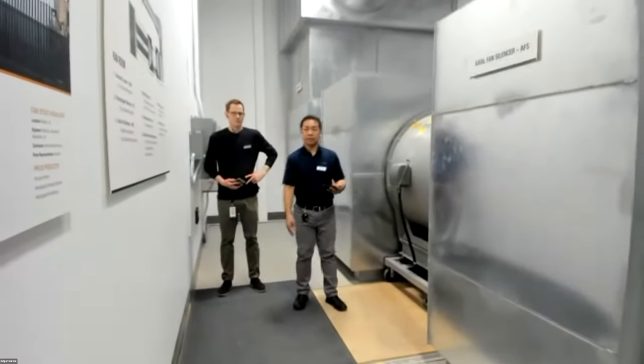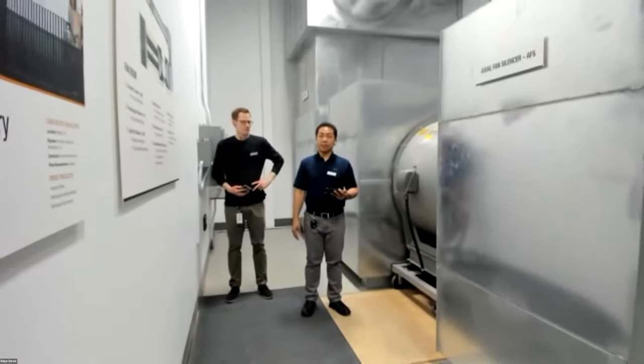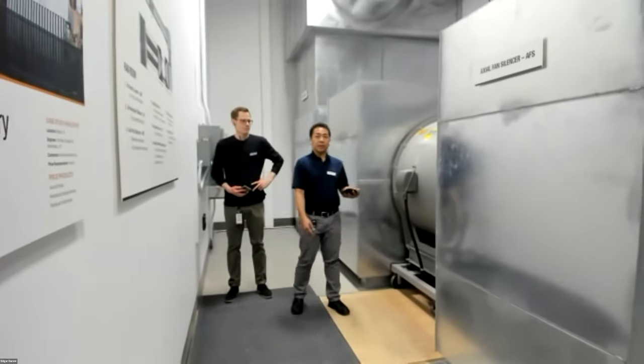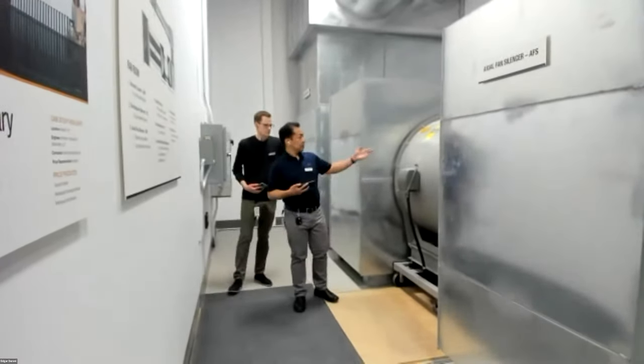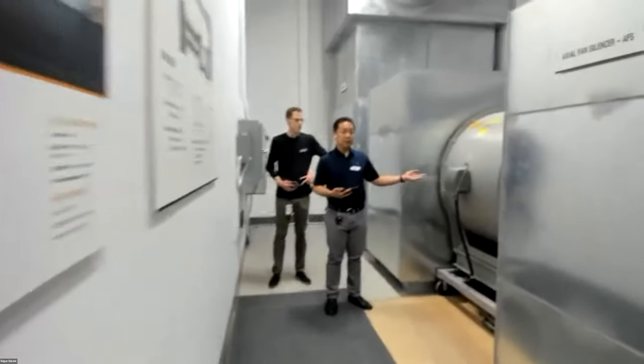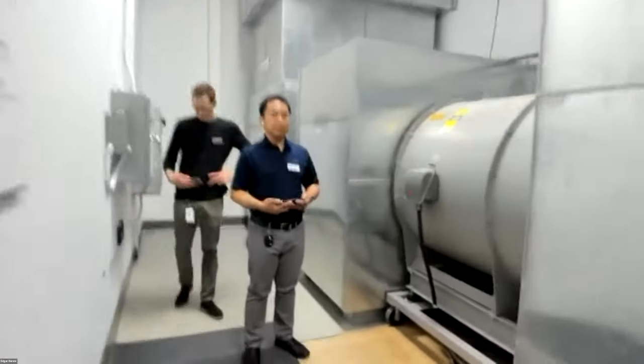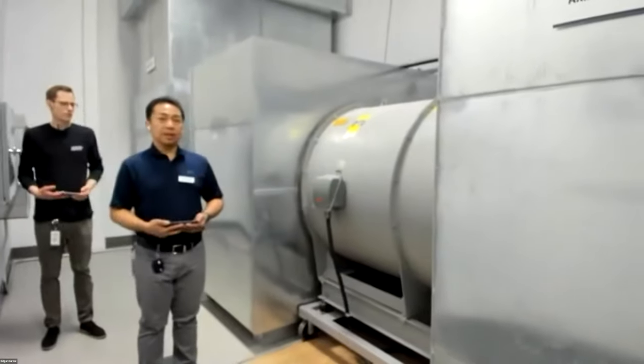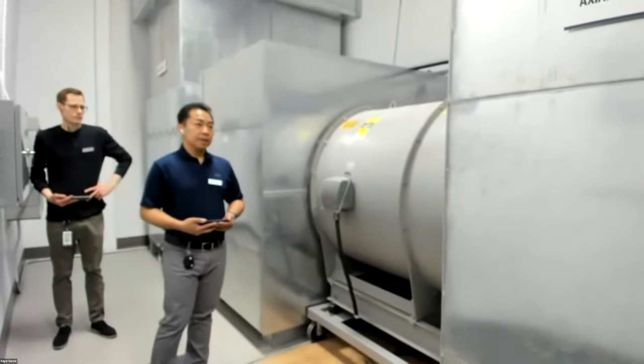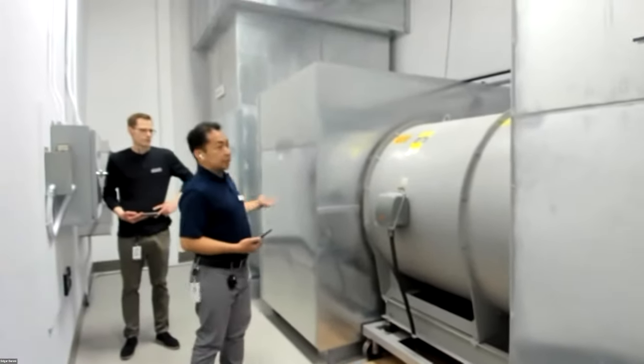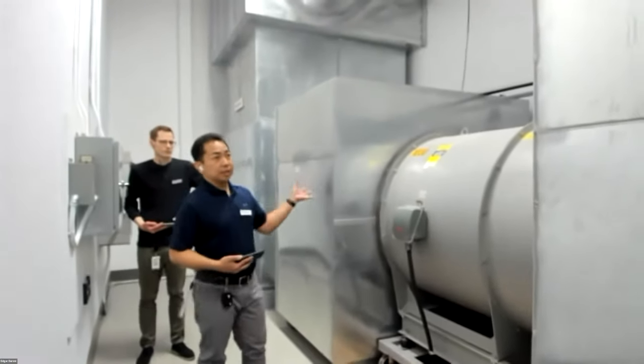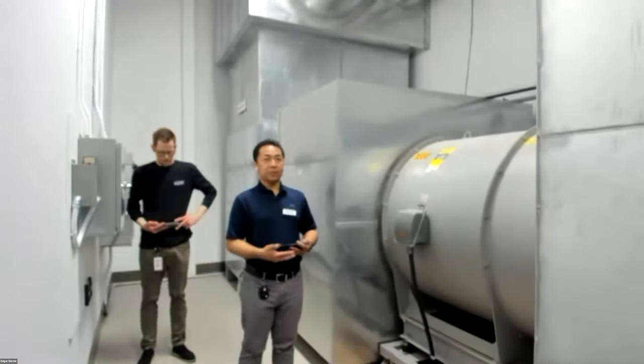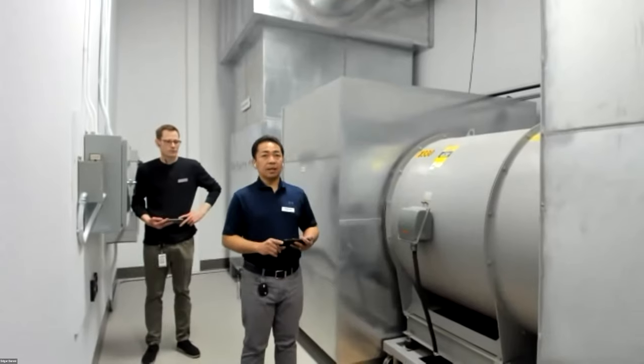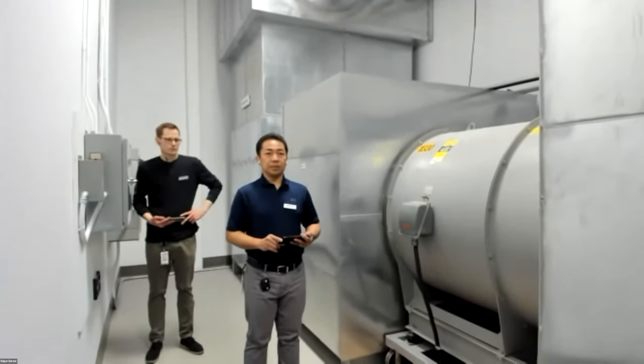So this is the first part of our four-part system. This is a fan room. We have here the reversible vane axial fan that can deliver up to 30,000 CFM at 4 inches of static. And we employ silencers on the inlet and discharge either way. Of course, this is reversible, so we can test the silencers in both supply and exhaust mode.